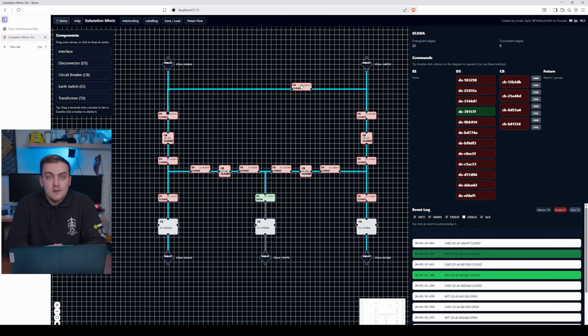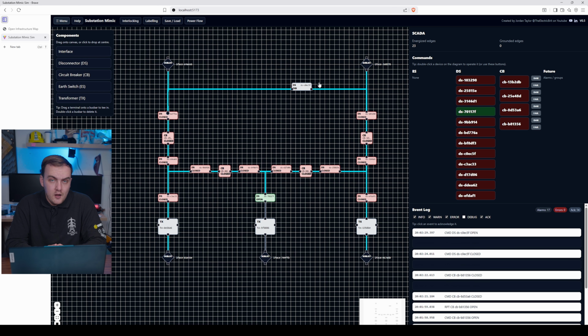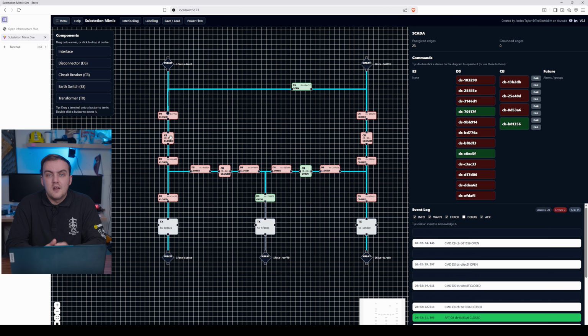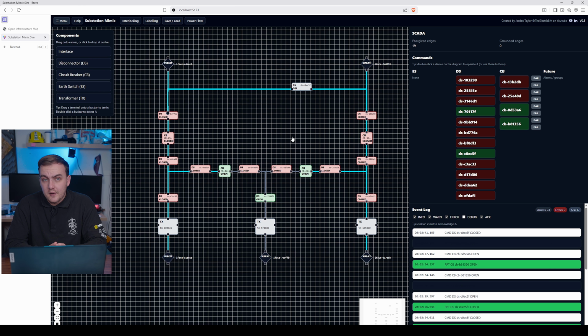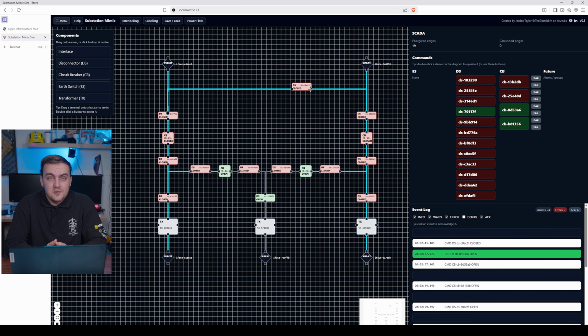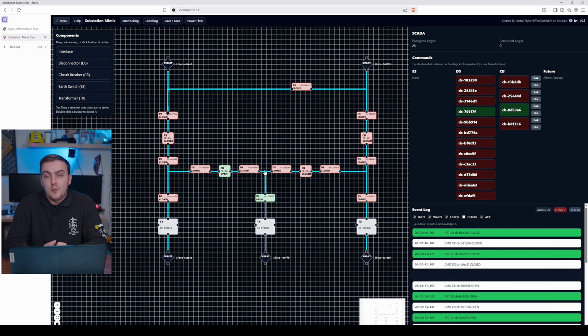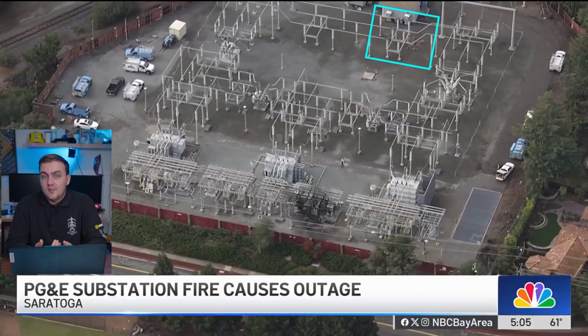Once it's open, you can then open your circuit breakers again and operate the substation as two distinct circuits. Closing this disconnector again operates the whole substation solid. This lets you bypass your circuit breakers on each circuit if one fails or is out due to maintenance. But operating your substation solid like this has the risk of tripping the whole substation under a fault, which is why it'll normally be left open like it is now. So that does it for layouts.